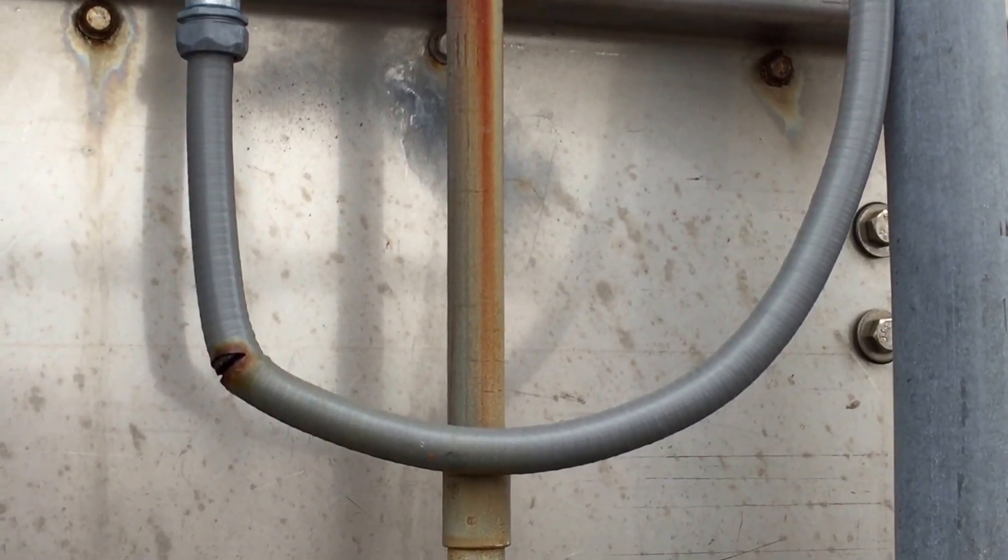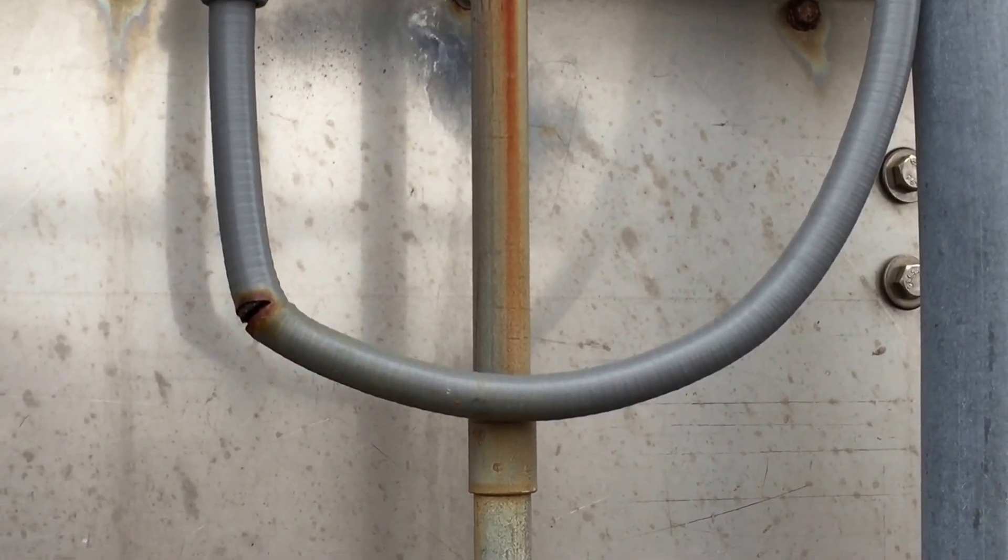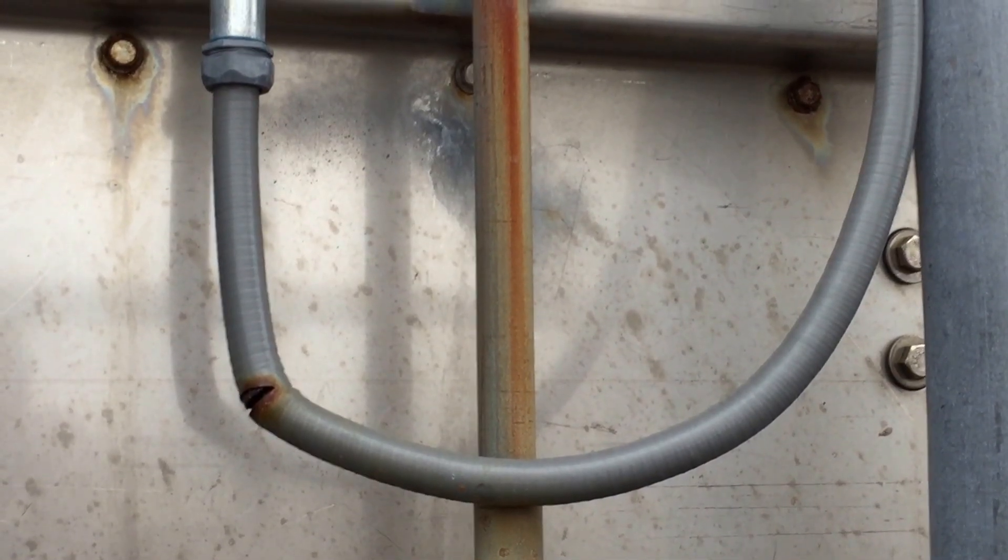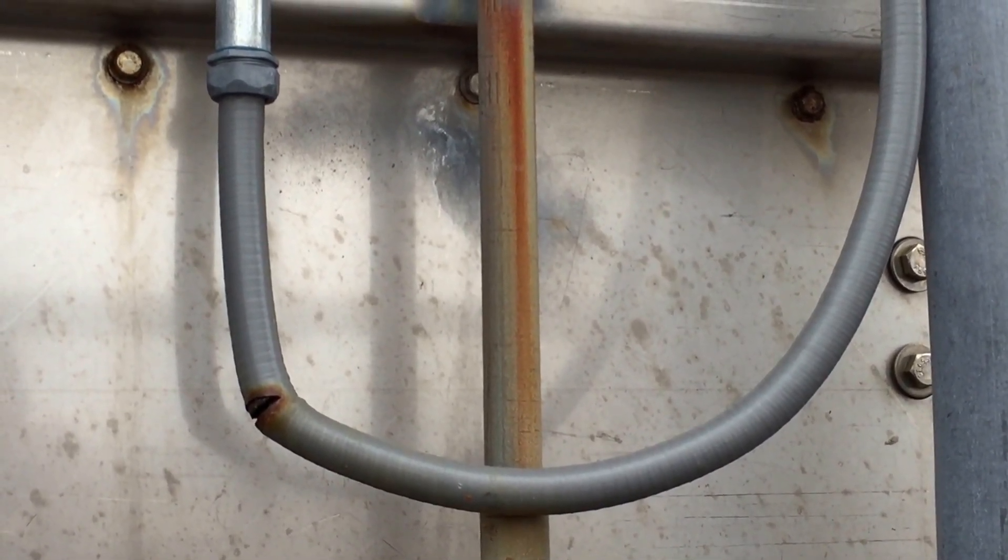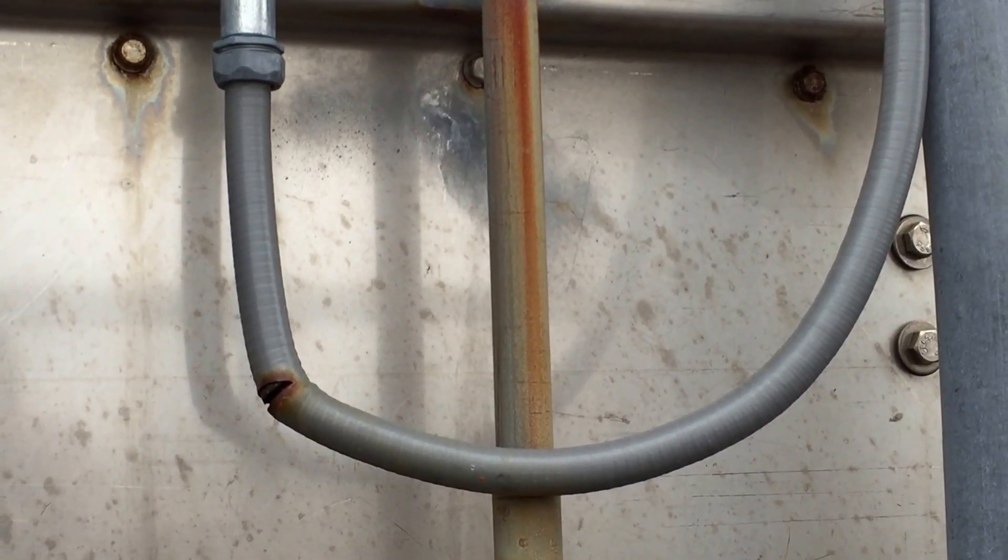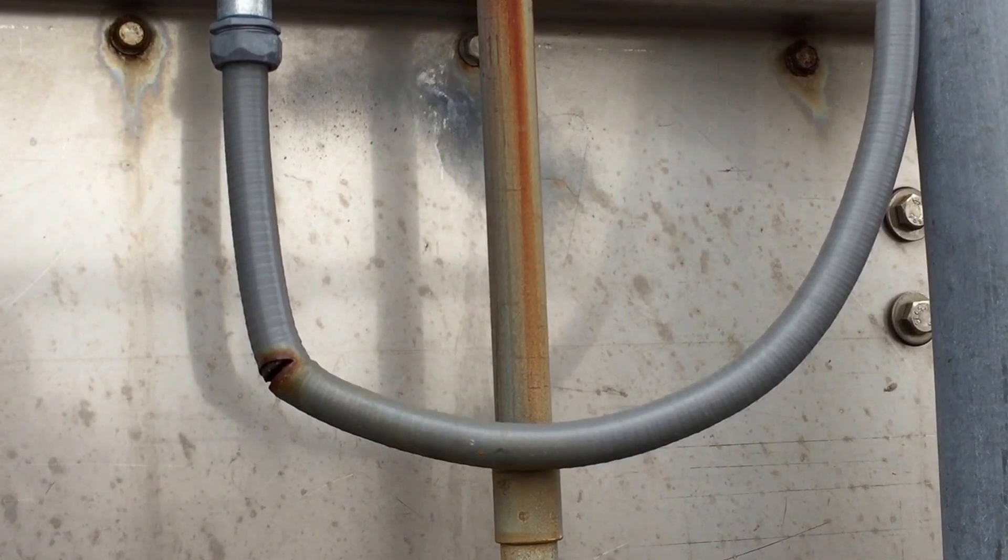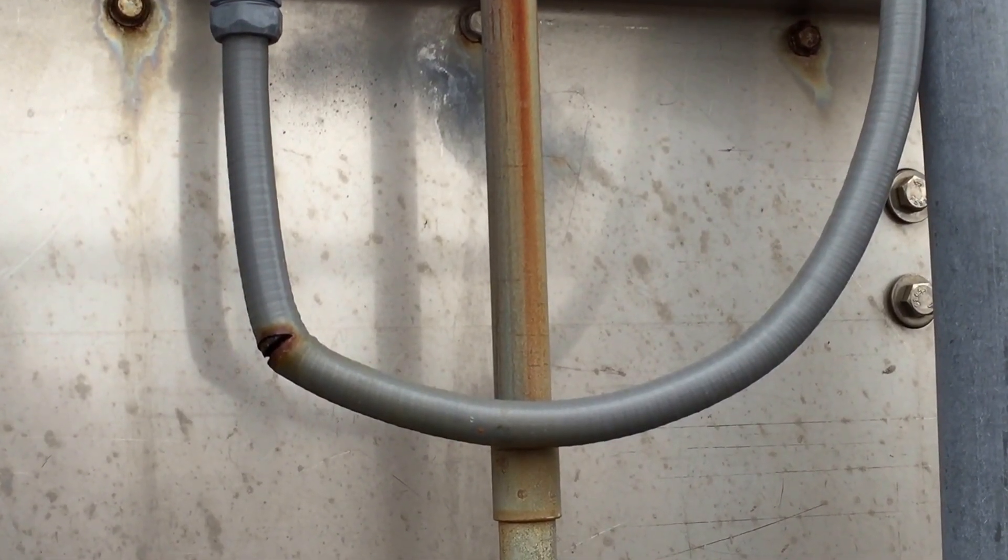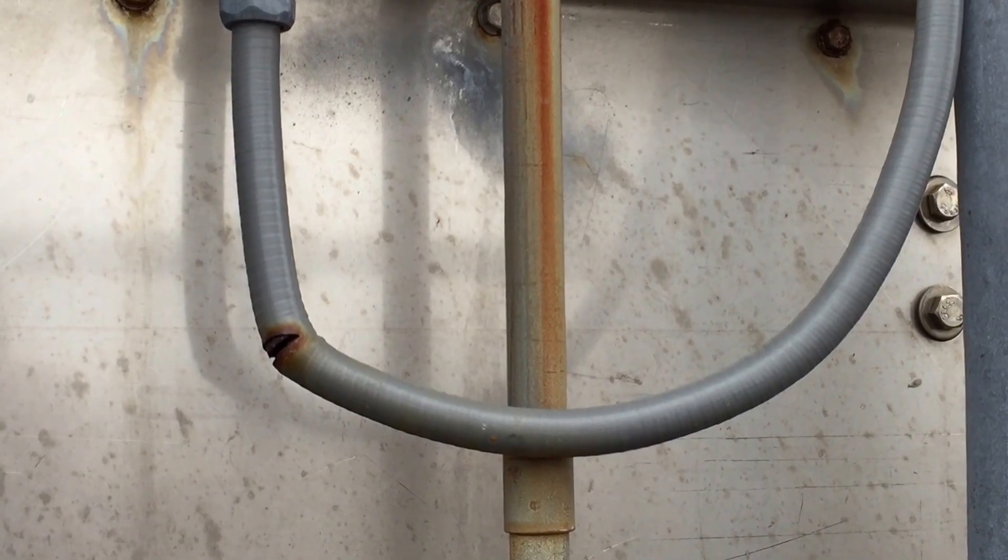Now, section 350.24 says that bends in liquidite flexible metallic conduit have to be made so as to not damage the conduit. But I think what happened here, these bends were a little too sharp, they kinked it, and damaged the non-metallic jacket, and this is the result.